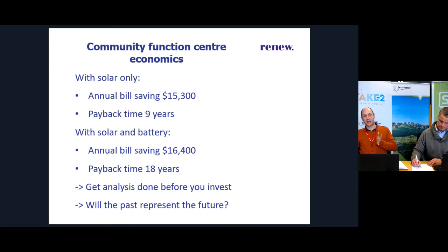Once you take into account the upfront cost of the battery, the payback time blew out to 18 years. And that's not too uncommon with the analyses I've done on batteries. When you look at the payback time of just that battery component, adding on that battery cost, you do get some pretty long payback times. So the key message, I guess, is get some analysis done before you invest a lot of money in an expensive battery.